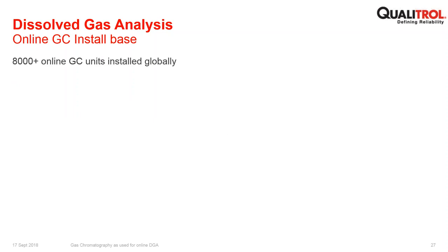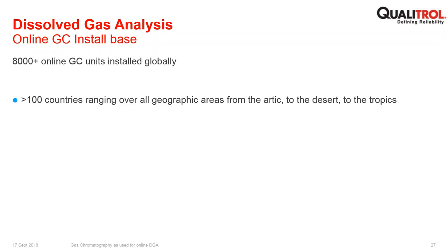For Qualitrol, and I think this may be the final slide or the second to last slide, there are 8,000 online GC units installed globally by Qualitrol. There are other manufacturers out there, so that number is even greater. It's a very, very well-established technique. It's been around as a field-deployed instrument since 2004, and in the case of Qualitrol, there are more than 8,000 in the field. It's used in more than 100 countries, from northern Canada or Siberia, to the Middle East, the deserts of North America, and indeed the tropics, Central America, Indonesia, the Philippines, etc. So it is suited to a wide variety of climates.